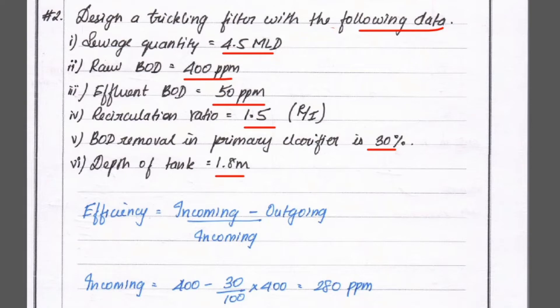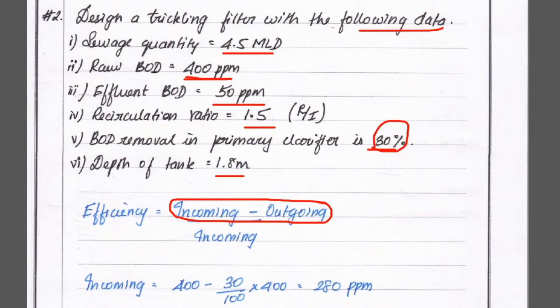We have to find out the diameter of the trickling filter. First, we find the efficiency: efficiency = (incoming BOD - outgoing BOD) / incoming BOD. The raw BOD is 400 ppm and 30% is removed in the primary sedimentation tank, so incoming BOD = 400 - 30% of 400 = 400 - 120 = 280 ppm.